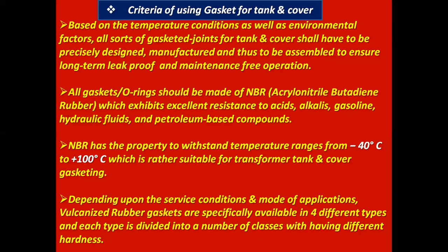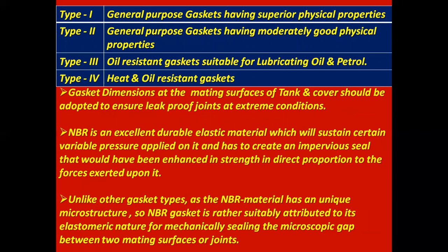and cover gasketing. Depending upon the service conditions and mode of applications, vulcanized rubber gaskets are specially available in 4 different types, and each type is divided into a number of classes which have different hardness. Type 1, general purpose gaskets having superior physical properties. Type 2, general purpose gaskets having moderately good physical properties. Type 3, oil resistant gaskets suitable for lubricating oil and petrol. Type 4, heat and oil resistant gaskets.